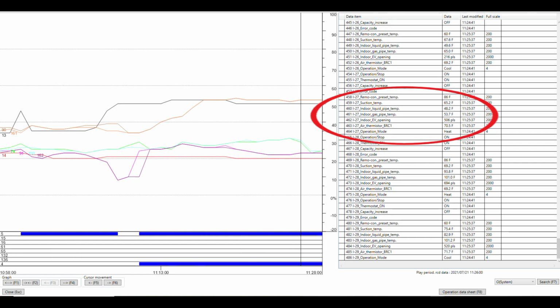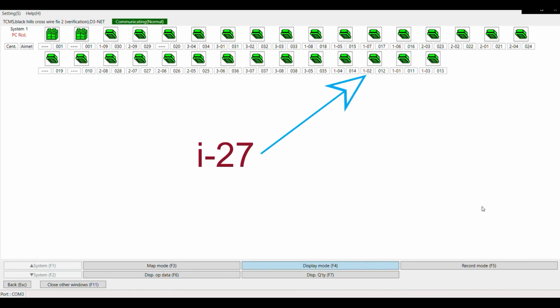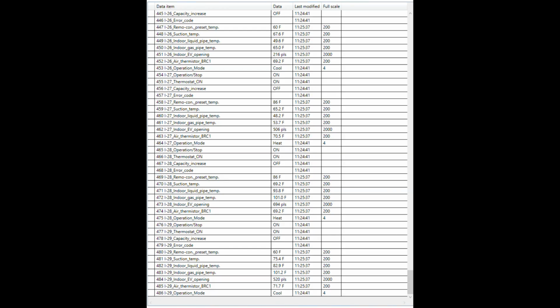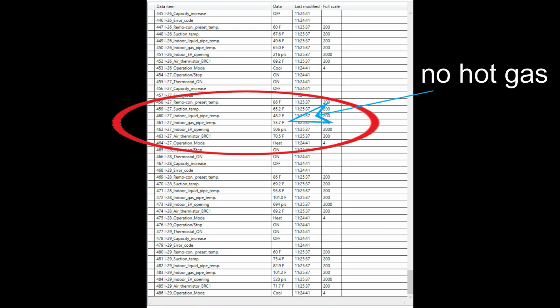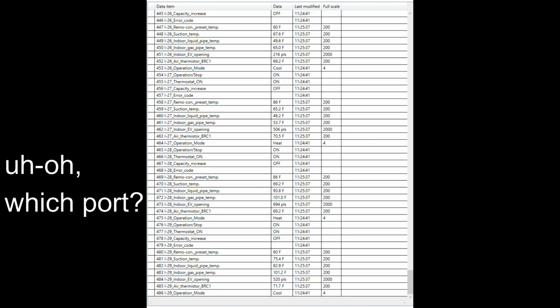You can see though we have a small problem. Group address 1-02, which is I27, is calling for heat but not receiving any hot gas to the indoor coil. We can see this by looking at the indoor unit gas pipe thermistor data value. This means that 1-02 actually got wired to a different port. We don't know which port though.